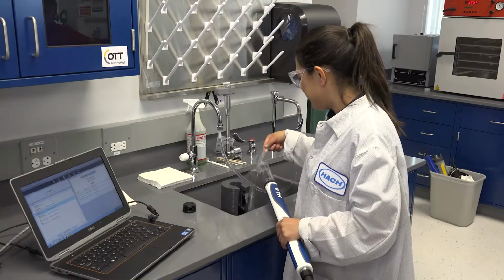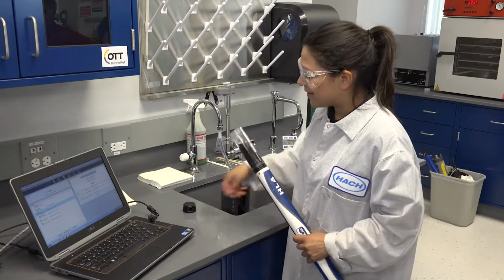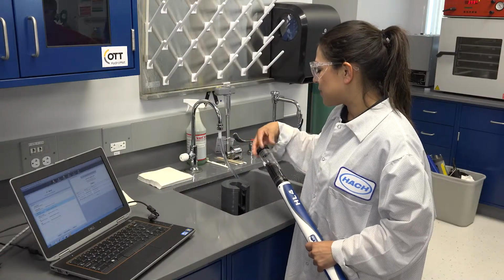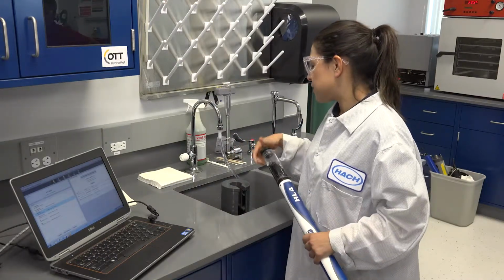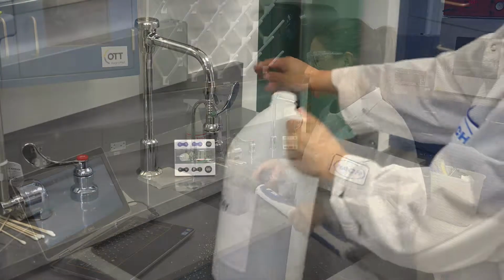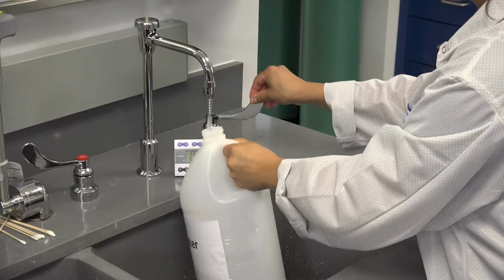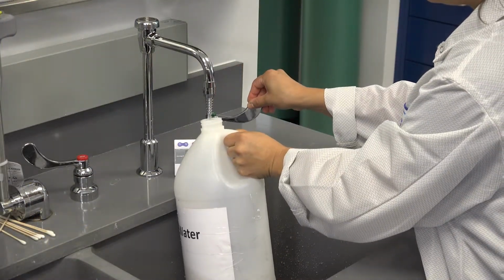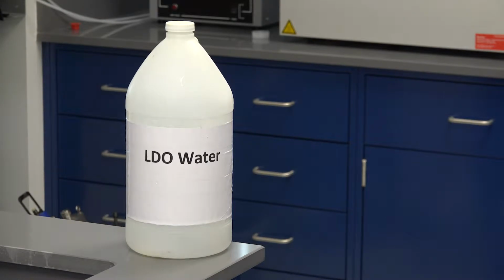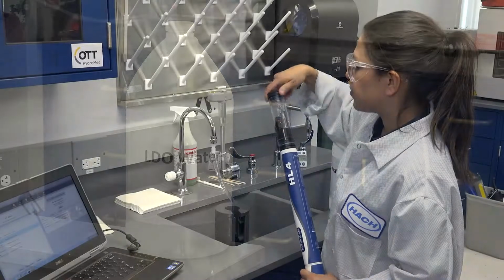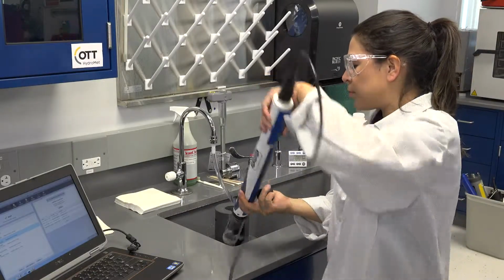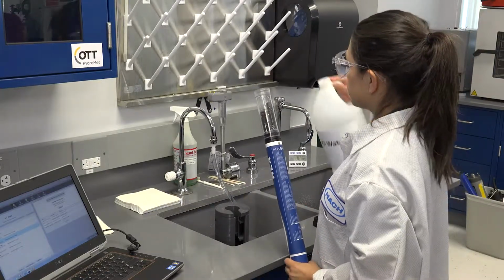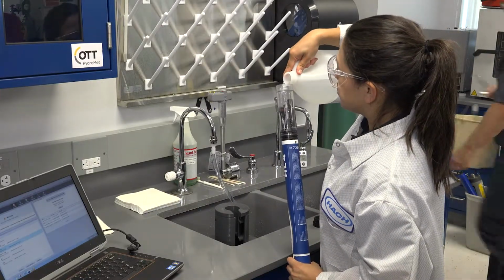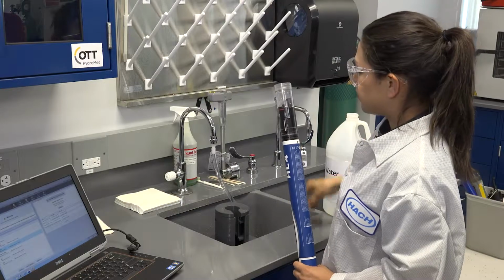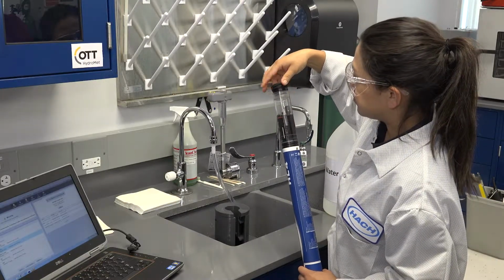Calibration. The LDO sensor compensates for the temperature of the water. To perform an accurate calibration, it is important that the temperature of the water remain constant during the procedure. The easiest way to do this is to allow the water used for calibration to sit overnight in an open container until it equilibrates to room temperature. If the temperature changes by more than 0.5 degrees Celsius during calibration, dissolved oxygen measurements may be inaccurate and the sensor will need to be recalibrated when the temperature of the water stabilizes.